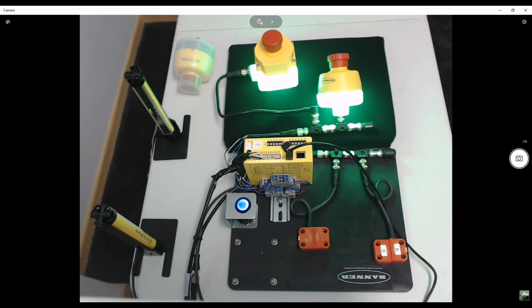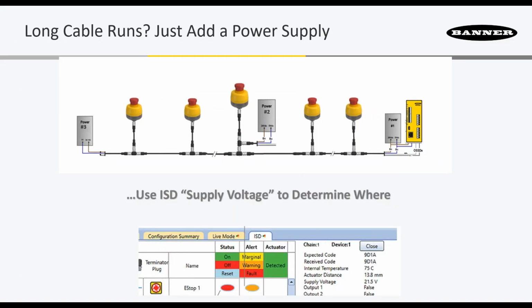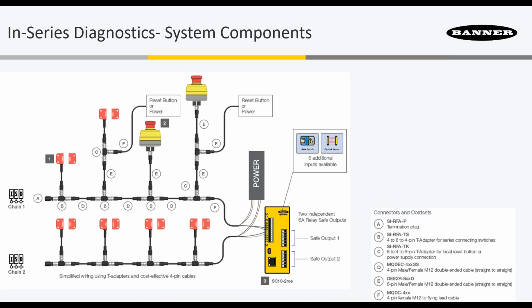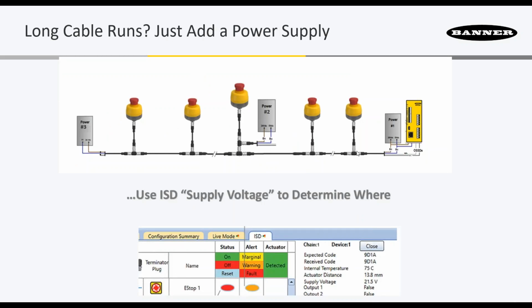Yeah, on that, so we really don't have a limitation other than there's a 30 meter limit - let me go back and show the screen here. Okay, so from the last device to the SC10, there's a 30 meter limit here. Other than that, there's no limitation, and as needed you can add power. That's really the biggest thing. Once you get below 19.2 volts, you need to inject power, and it's a very simple method, either using a T-connector or replacing the termination plug.